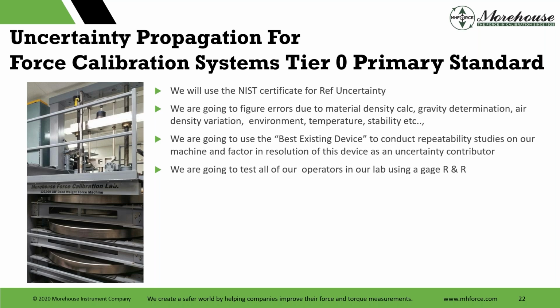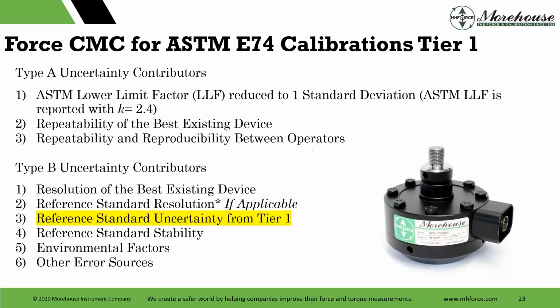The other thing we're going to do, typically there's this talk in some of the guidance documents about best existing device. So we're going to use a best existing device to conduct repeatability studies. How do we know how good our equipment is, right? Unless we can do the propagation, unless we put equipment in there, start to run process control charts and start to do other things and start taking a lot of measurements, it's just numbers on paper at some point, right? So you haven't actually put something in a machine. It could bend, it could do all types of things. You could introduce side load, all types of error sources are present. What I like to say for force, if the best machines are plumb, level, square, rigid, low torsion, and you are never perfectly level, you always have torsion, you always have some bending in the system, so you can take it from that.